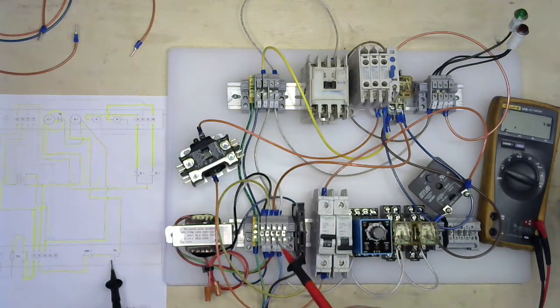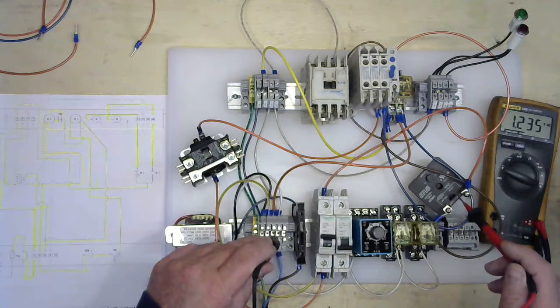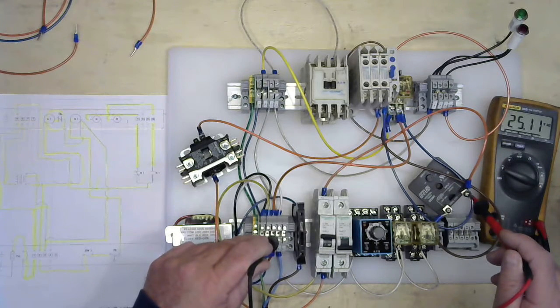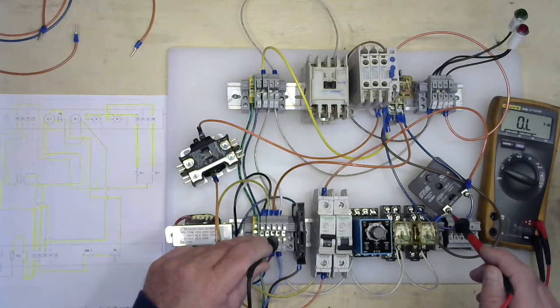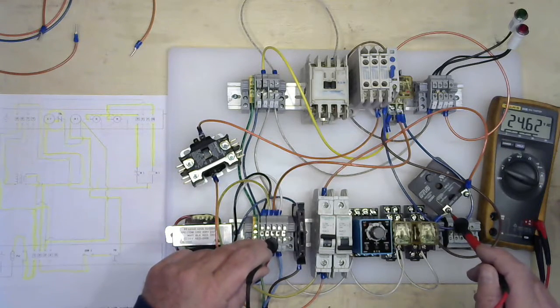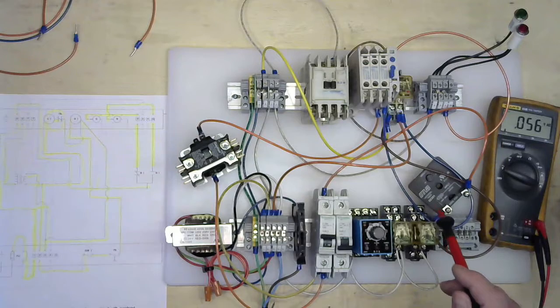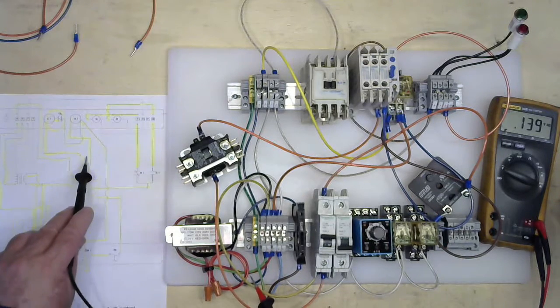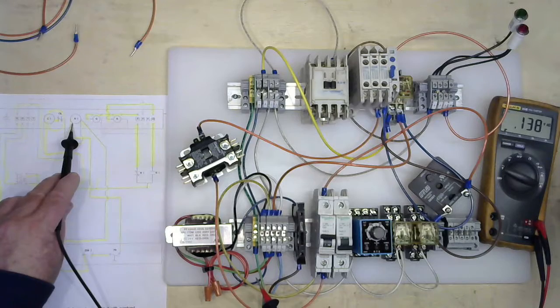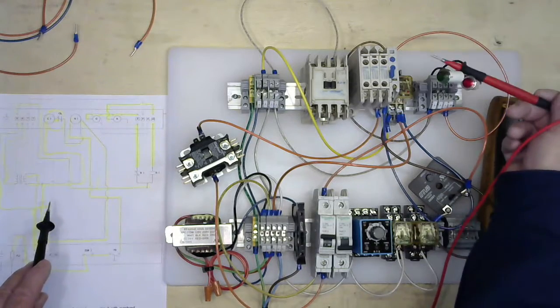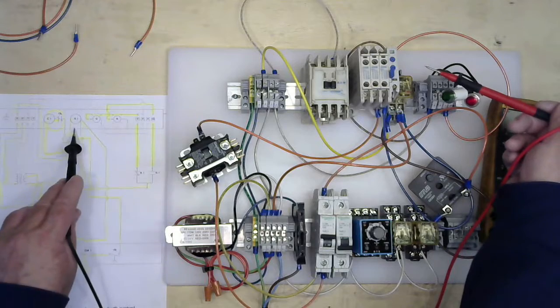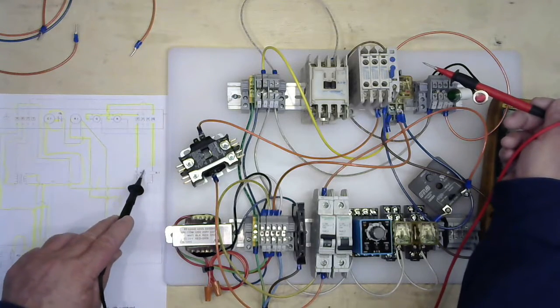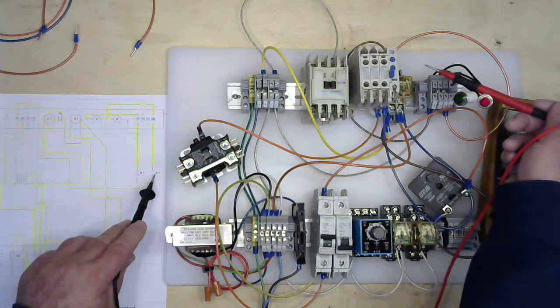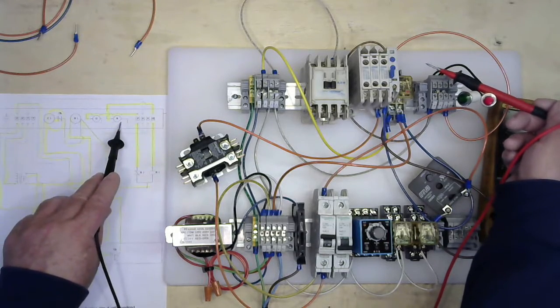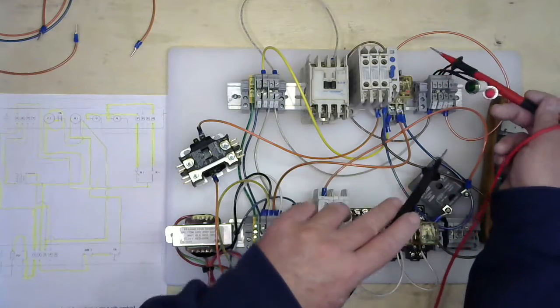So that means I should have power going to my input of my time delay relay. I'll check over here at my input, and I have power. Now do I have power on my output? Now I do. I didn't for a second there, but I have my time delay set up differently. So once the time delay finishes, I'm going to energize my relay, and that's going to change the state of my light. So when the relay coil is energized, my contacts here are going to change. My normally open contacts are going to close, powering up my red light, which is on now, versus my green light.